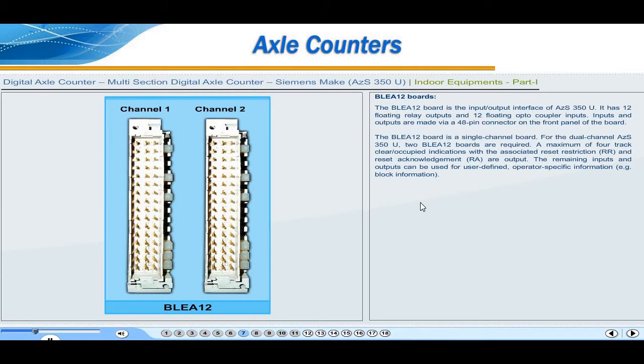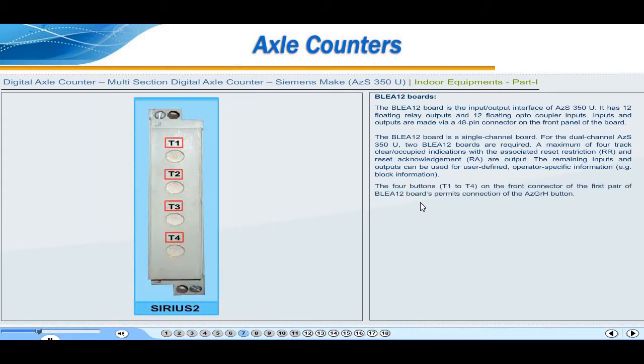A maximum of 4 track clear or occupied indications with the associated reset restriction, that is RR, and reset acknowledgement, that is RA output. The remaining inputs and outputs can be used for user-defined, operator-specific information, for example, block information. The 4 buttons, that is T1 to T4, on the front connector of the first pair of BLEA12 boards permit connection of the AZGRH button.